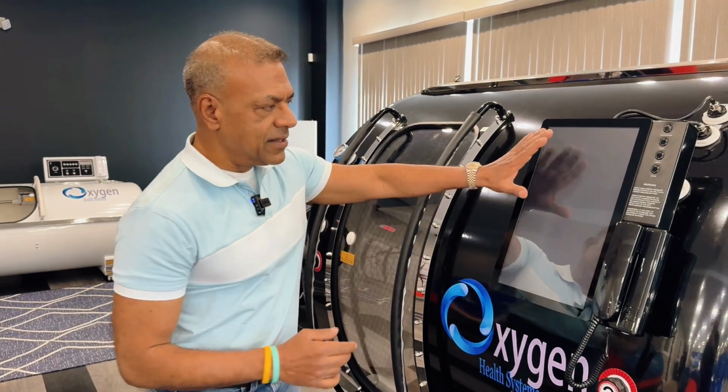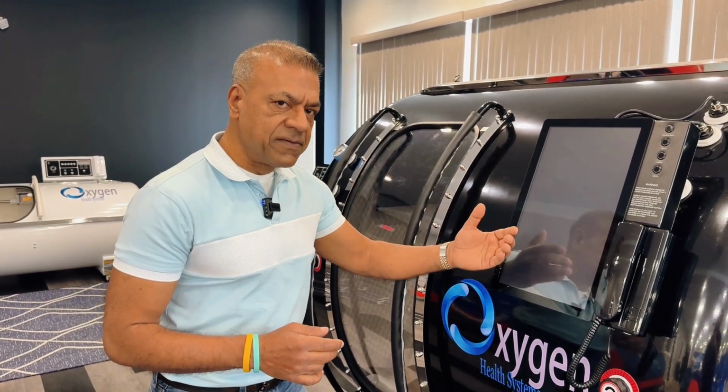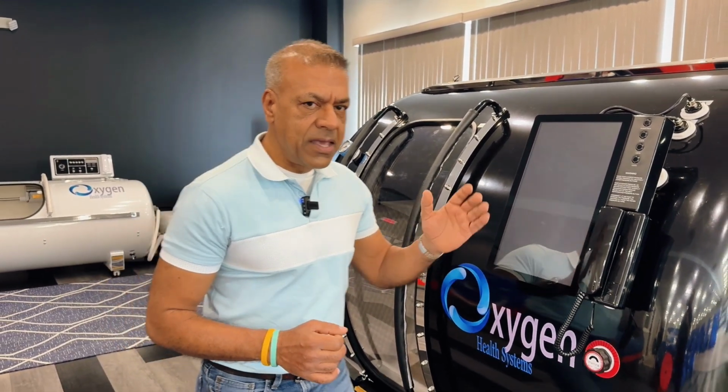So what we have done, we have induced a power outage intentionally. And notice the entire screen or user interface went blank, and I'm also hearing the sound that the machine has begun the depressurization process automatically. So to answer your question in terms of your concerns, would there be any danger or anything of that sort if the power should go out?